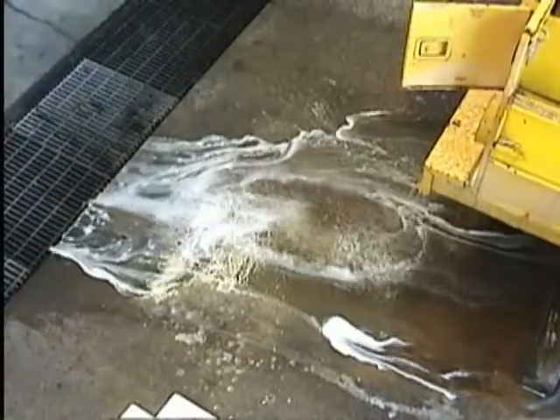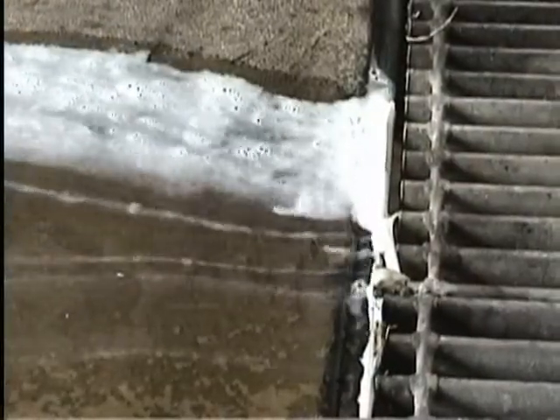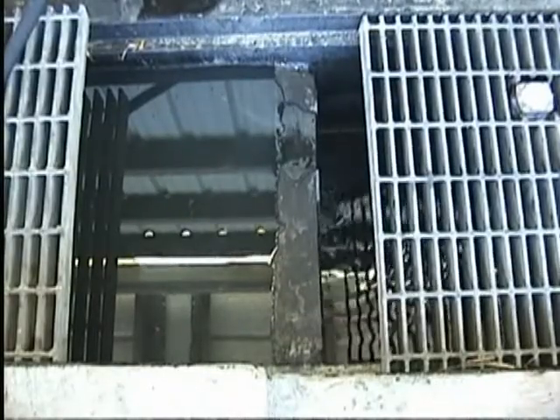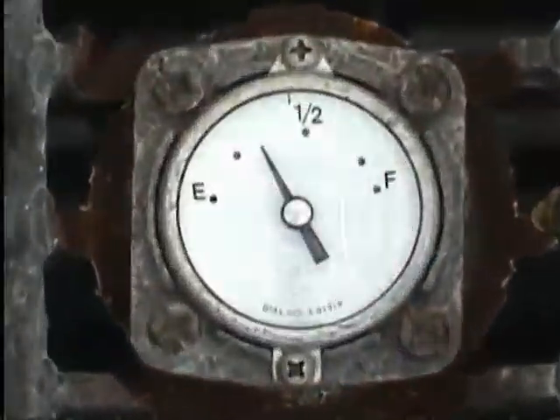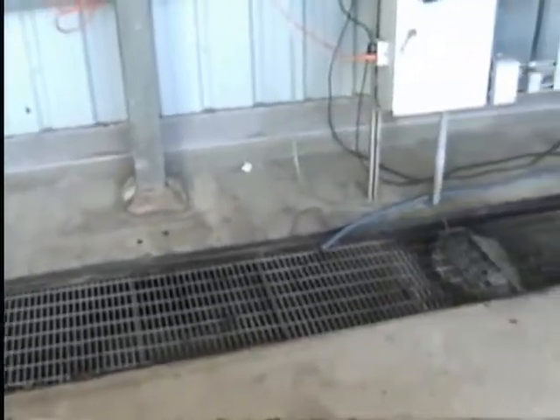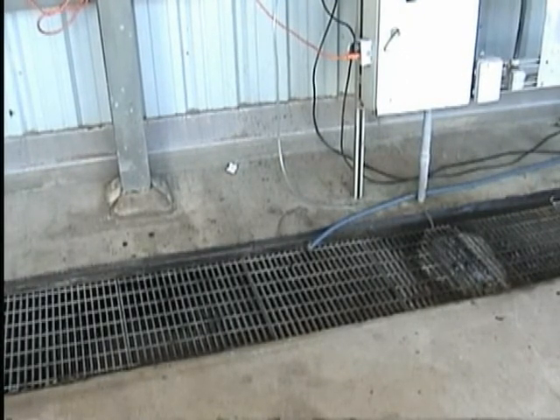While washing equipment, the wastewater flows into either the east or west collection sump, depending upon which bay the equipment is in. The west collection sump has 2 purposes. It collects wastewater produced while washing equipment in the west wash bay and acts as a capacity surge overflow containment. To maintain the capacity surge capability, the west collection sump is maintained below the half-full level as much as possible. The east collection sump collects wastewater produced from washing equipment in the east wash bay and serves as the location for the gravitational separation and aeration with agitation waste treatment processes.